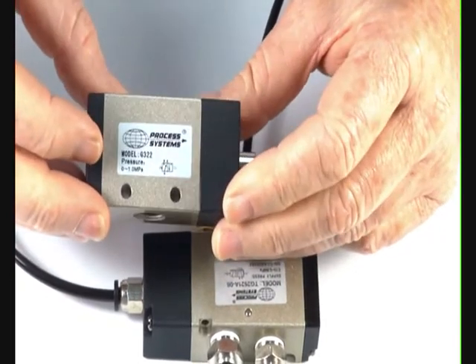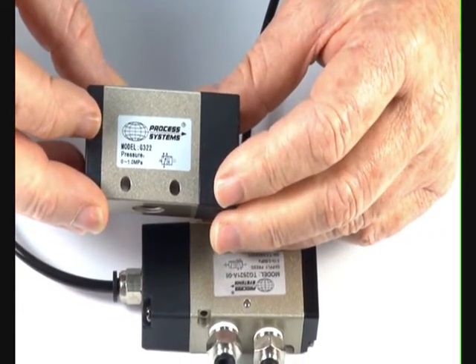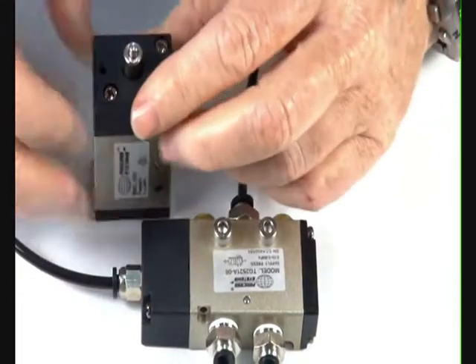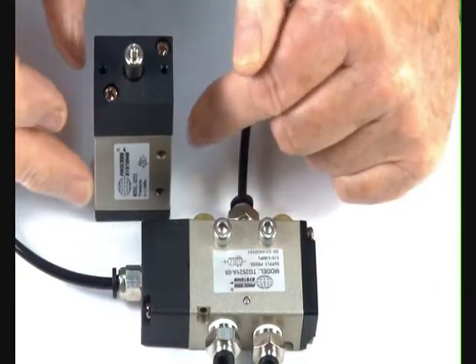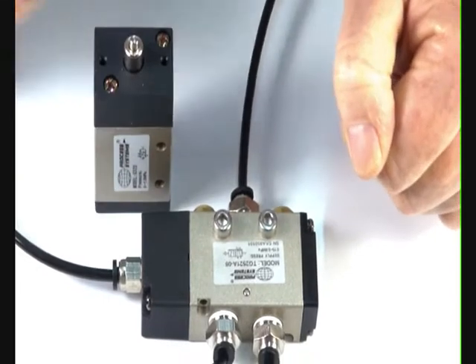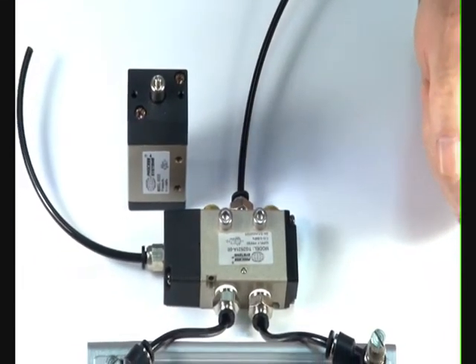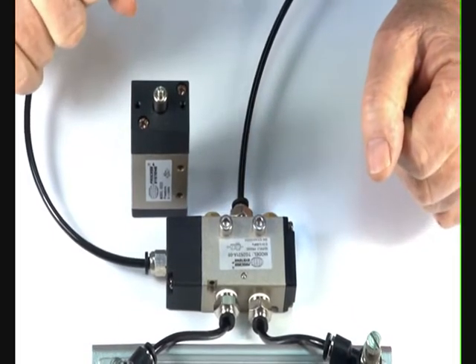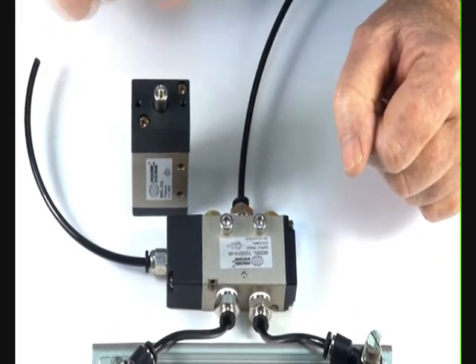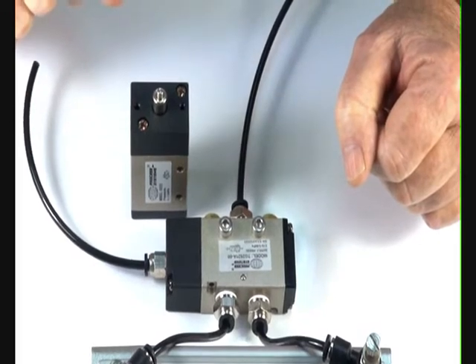Now this valve here can also be piped up normally open or normally closed. In other words, when the air is on the inlet port at the base, there's no air coming through until the valve is operated. If you put it into the other port, when the valve has not been operated, the air is passing through. That's a normally open situation.